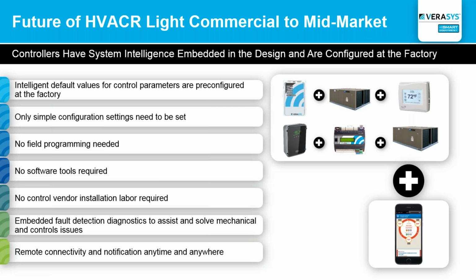What we've done with FDD is provide an embedded FDD solution within our equipment. For example, within our rooftops we monitor the refrigeration cycles, and we have algorithms embedded within our controllers that let us identify an actual fault before there's a major failure.